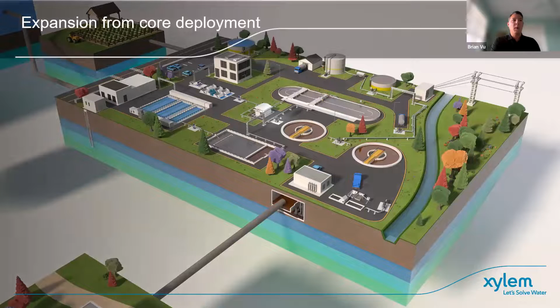So where can we add this type of technology? We talked about this briefly, but this is a plant overview. We're going to focus today a bit on aeration, and how we can optimize or add automation within it. You can do this in activated sludge and aerobic sludge plants, in gas controls—if you're producing gas from anaerobic digestion, gas cleaning systems are highly automated, not something you'd want to manually run. We can do power distribution, using that gas to produce energy, which gives you a chance to control switch gears remotely through SCADA. We can add this into disinfection, whether UV or chlorine, both can be automated. Sensors are key, and we'll get into why.